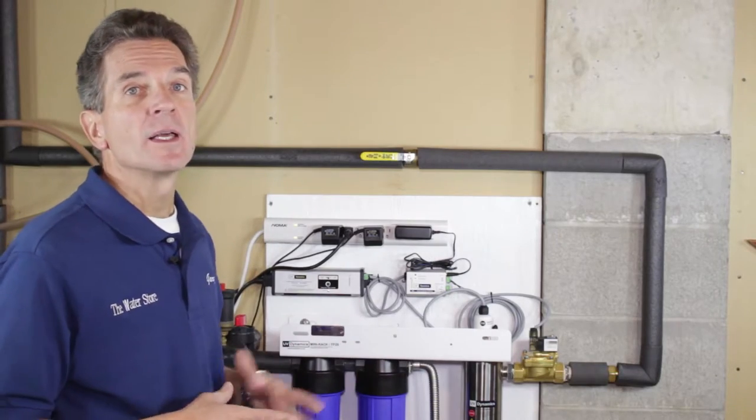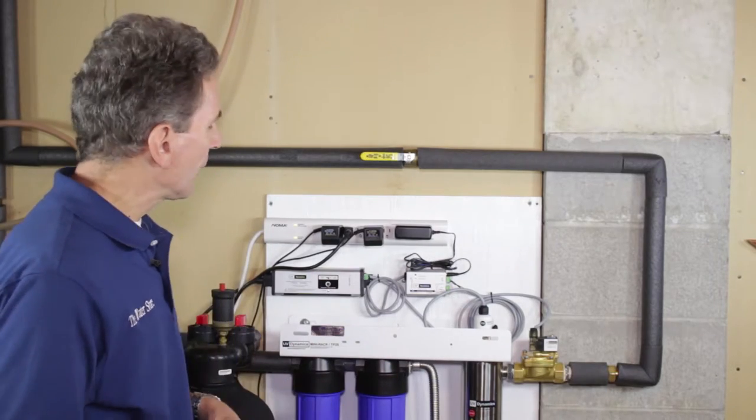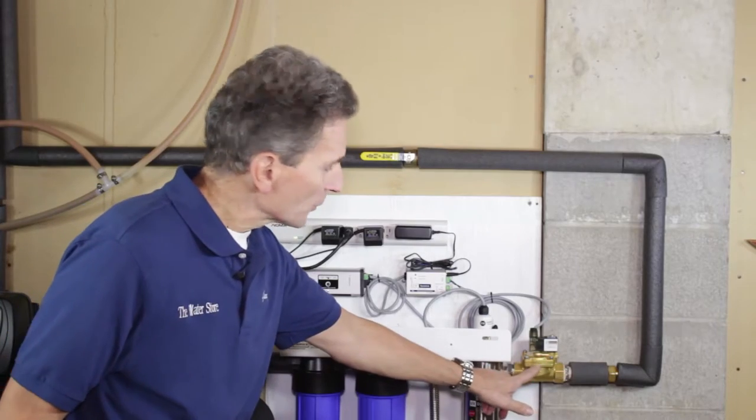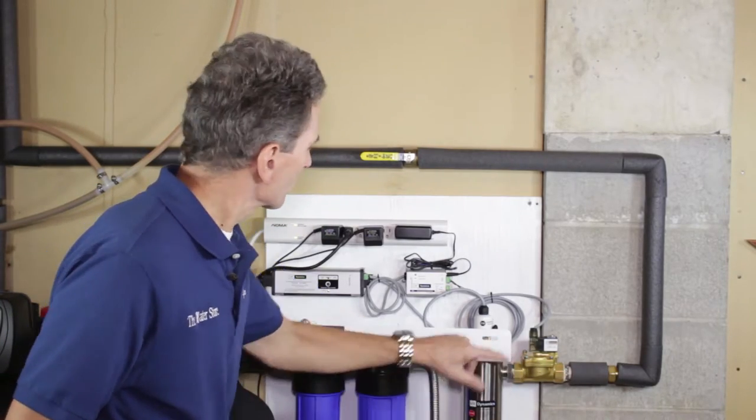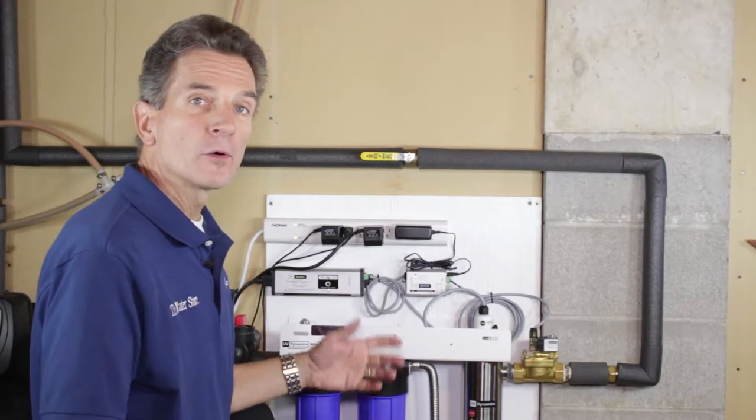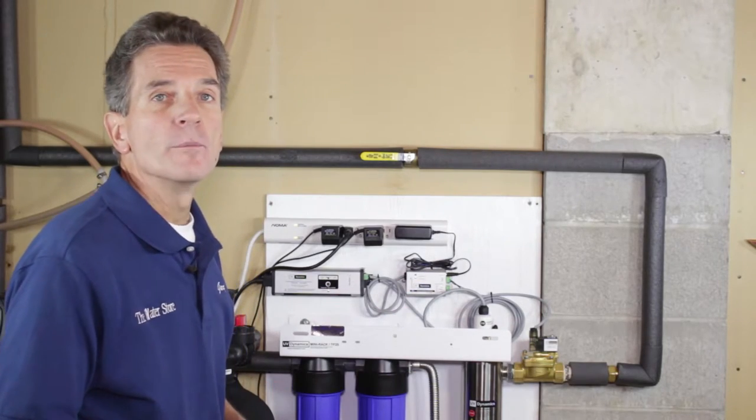So this UV dynamic system here obviously is, and so this is the actual solenoid valve itself. It's installed after the ultraviolet light, and then this is the controller here. So if the power goes out, it shuts off the water flow immediately.